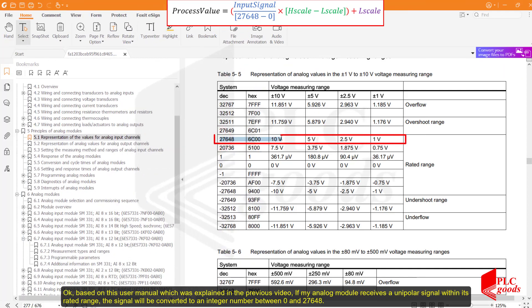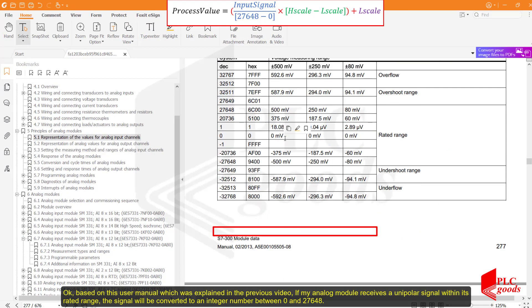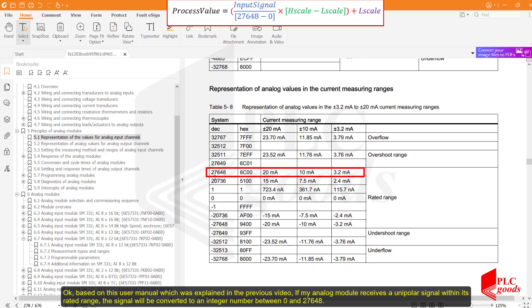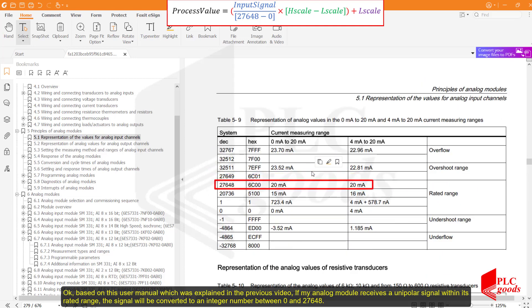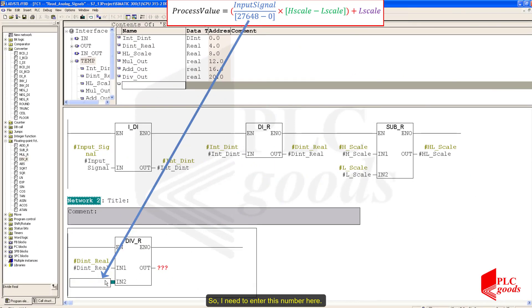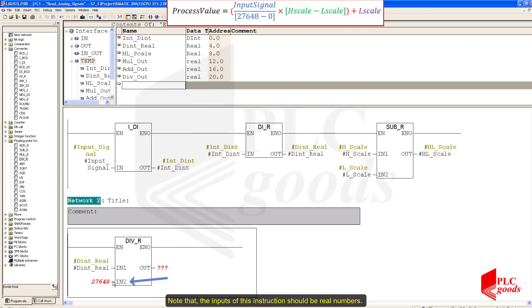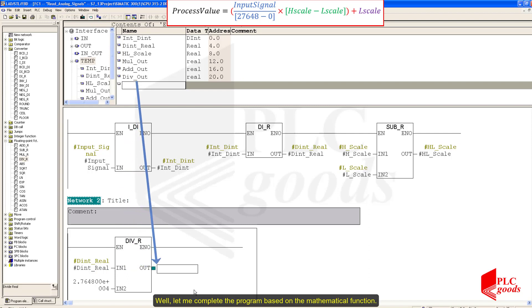Based on this user manual, which was explained in the previous video, if my analog module receives a unipolar signal within its rated range, the signal will be converted to an integer number between 0 and 27648. I need to enter this number here. Note that the inputs of this instruction should be real numbers, so I need to add the fractional part: 27648.0. Let me complete the program based on the mathematical function.